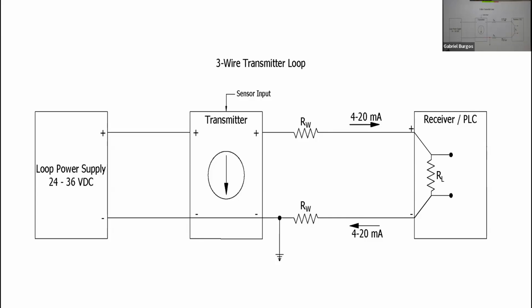Now, what's the difference between 2-wire and 3-wire? 2-wire are very popular with people that don't want to use a lot of wire or have long runs, because the copper costs money, and it's gonna cost a lot more in days to come. 3-wire has the advantage that you still only need 2 wires going out to the device, going back to your loop. And you can put the power supply, for example, inside of an explosion-proof box or something else. The 3-wire transmitters are much cheaper than 2-wire transmitters as well. To give you an idea, it's usually a 2-to-1 factor. A 3-wire transmitter might be $300, and a loop-powered transmitter is $550 or $600.